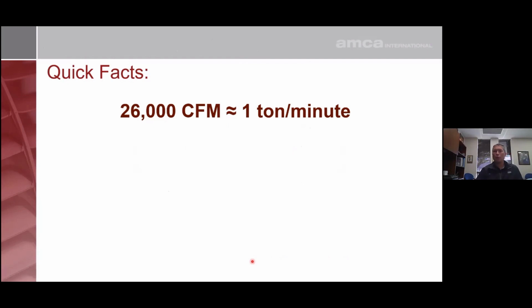Okay, before I go on to the final snippet of information, let me go through some quick facts. People always get upset with me, but I love to give little fonts of information. As I went through in the presentation, if you're moving 26,000 CFM of air through a fan, you're approximately moving 1 ton of air a minute. I think this is where people get in trouble: they just don't realize the mass flow going through the fan. It is pretty significant. And if you double it, you're moving 2 tons of air through the fan a minute. So it's a pretty significant number.